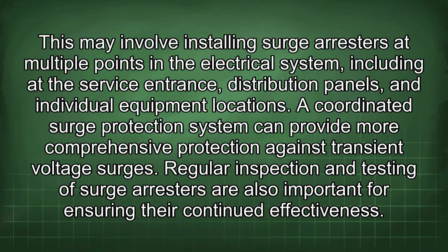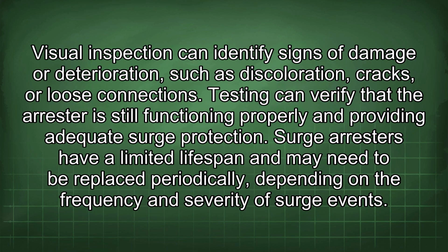Regular inspection and testing of surge arrestors are also important for ensuring their continued effectiveness. Visual inspection can identify signs of damage or deterioration such as discoloration, cracks, or loose connections. Testing can verify that the arrestor is still functioning properly and providing adequate surge protection.